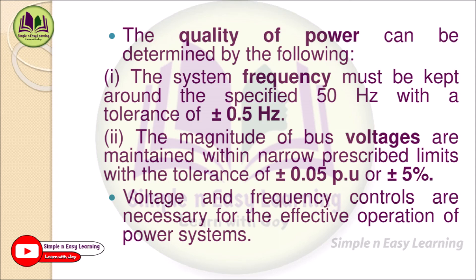From load frequency control to system planning, this forms the hierarchical control structure of the power system — lower order and higher order controls. The two main quantities that decide power quality are frequency and voltage. System frequency must be kept around the specified 50 Hz with a tolerance of plus or minus 0.5 Hz, meaning frequency is maintained between 49.5 and 50.5 Hz. In practice, Chennai maintains frequency very close to 49.9 Hz, only reaching around 49.7 Hz in emergency cases.